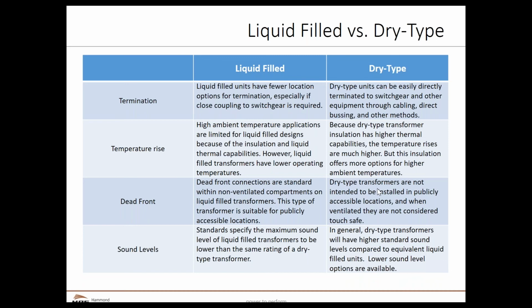And you have to be careful when you say dead front construction. Typically, the way we would interpret that with a dry type is we bring all the connection points into a separate terminal, often called an air terminal chamber. And then we have a dead front construction on that specific air terminal chamber. However, there are additional access points to the main transformer, and those are typically open because we would have some difficulty in blocking those off with some type of dead front construction because of the cooling characteristics. Again, you can do it, but it's not really the way most people would.